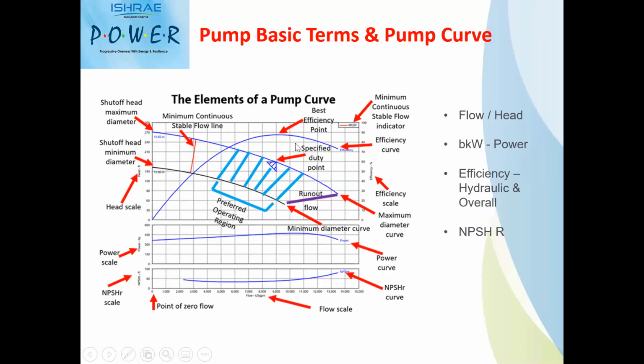And each and every pump will have a best efficiency point. The point where the maximum value of the efficiency is arrived is called the best efficiency point of a pump. This is the duty parameter, as I told. And then where the pump curve ends on the flow side, it is called runout flow, where the pump cannot take flow beyond this value for a particular size of the pump which is selected.